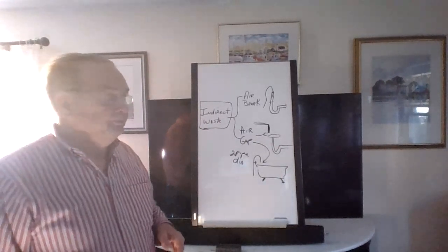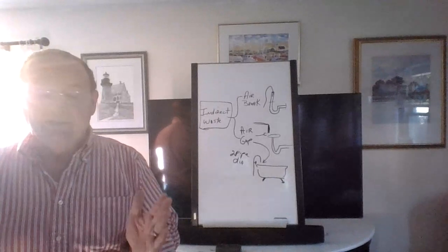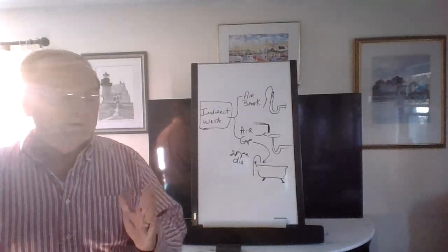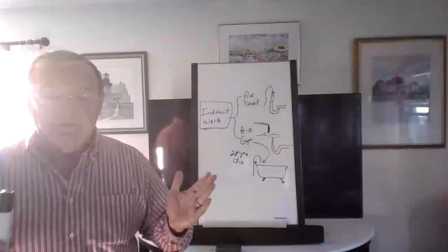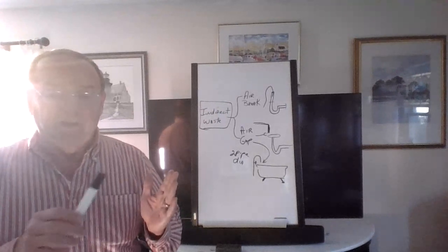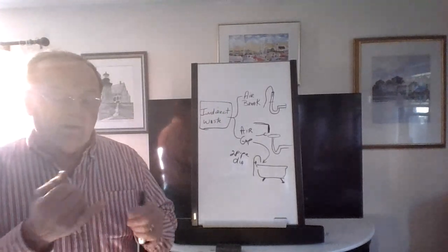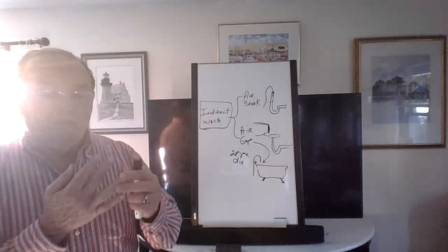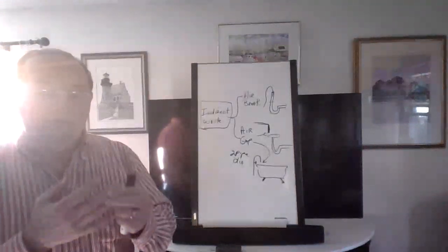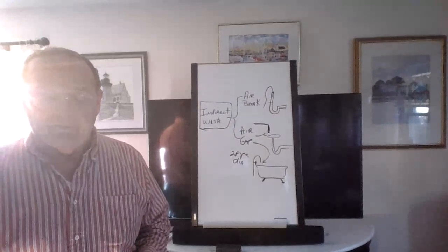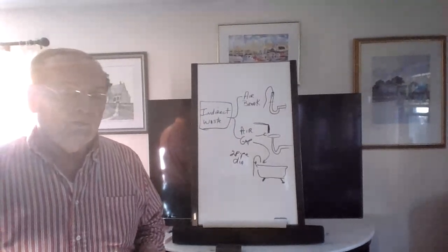The only connection between a heating system, hot water heating system, and a plumbing system is the makeup water, right? Which is obviously coming off the cold with a shutoff. So you're going to need a shutoff, backflow preventer, and a pressure reducer. Your town water or your city water, or even your well water, the pressure is going to be too high.